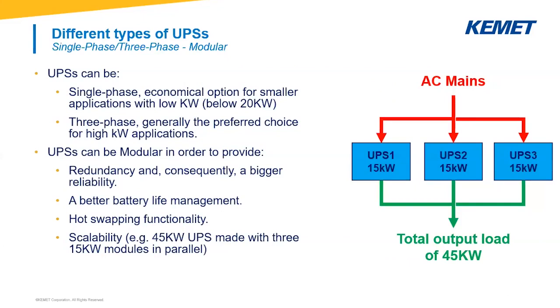We can see on the market different types of UPSs. We can divide them into two big classes: single-phase or three-phase. Single-phase is the most economical option for smaller applications — below 20 kilowatt in general. Three-phase UPS is generally the preferred choice for high-kilowatt applications. Another big trend we see in recent years is the modularity of these devices.